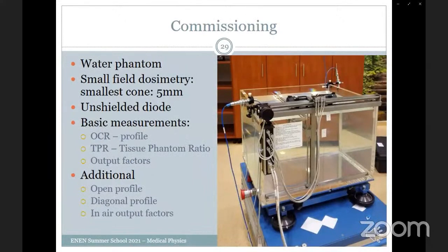The commissioning of the machine is quite complex. We are using a water phantom and we have to use small field dosimetry because the smallest cone that we are measuring is a 5 mm cone, so we have very small fields that we have to measure. We have to use an unshielded diode. Usually we use a so-called microdiamond during our measurements, which has a very small sensitive volume to be able to measure these small fields. We do profile measurements, tissue phantom ratio measurements, and we measure the output factors, and we had to do some additional measurements.